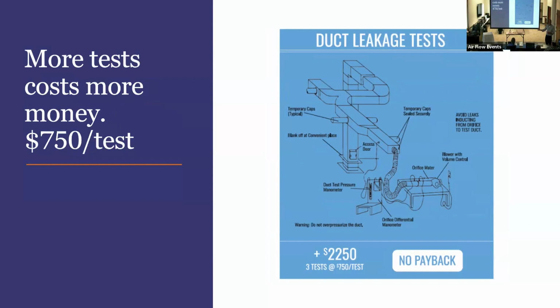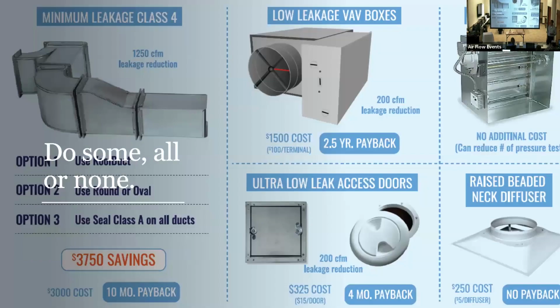Just test more ductwork. Don't test 0. And maybe instead of testing 25%, you do 25% high and 25% low. See what you get. And if they fail, hey, write that in your spec. If you fail, you gotta test more. Okay, and then, again, we're gonna talk about boxes in a second, use ultra low leak access doors.